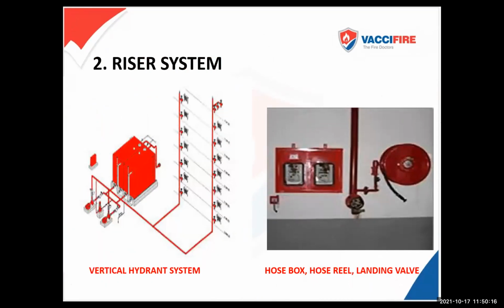Then we saw in the video there is a riser - a red line charged with water. This is the schematic of that system: you've got an underground tank, pumps installed there, and a line running through the pump. When this system is pressurized at the pump in the basement, the pressure is transmitted throughout the building by Pascal's law, undiminished, so you have the same pressure across the entire pipe.